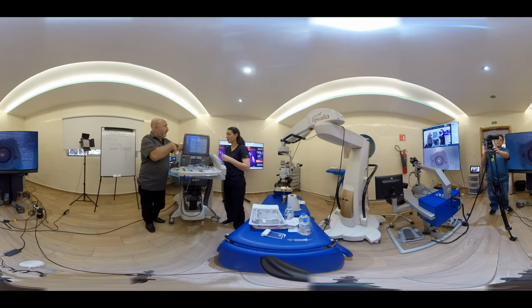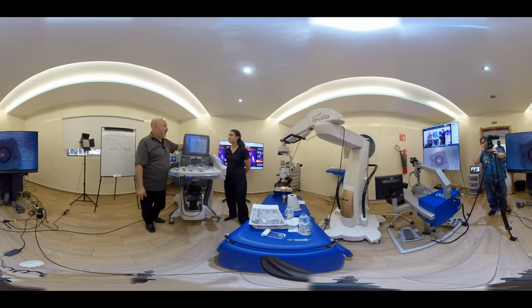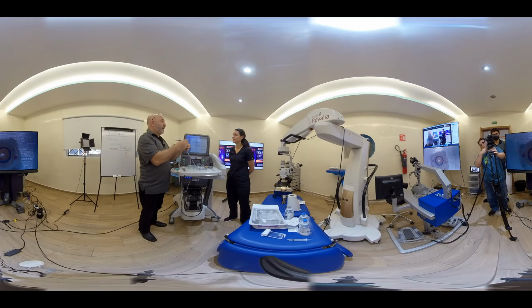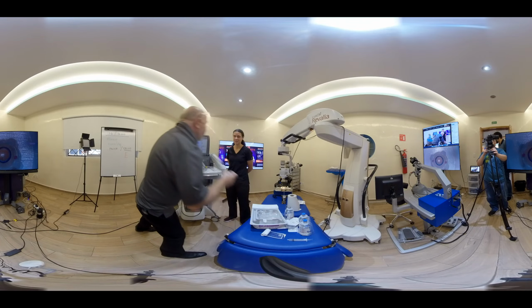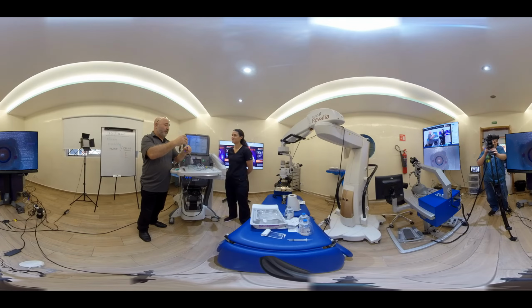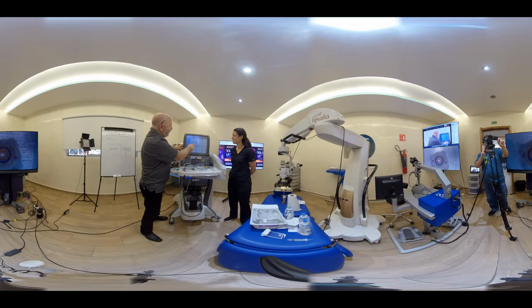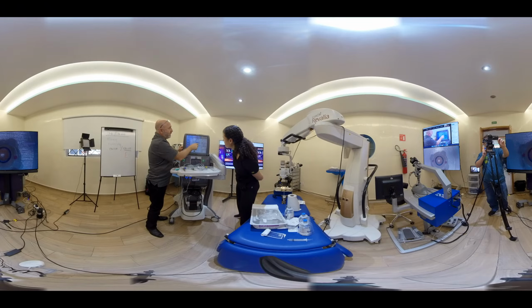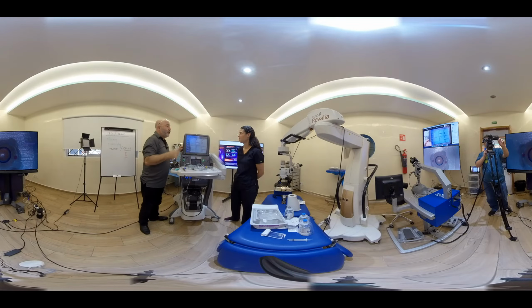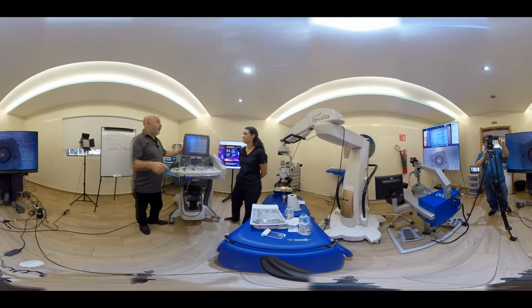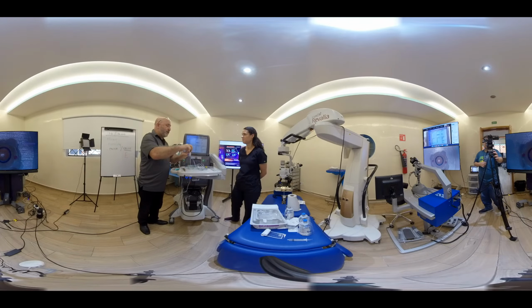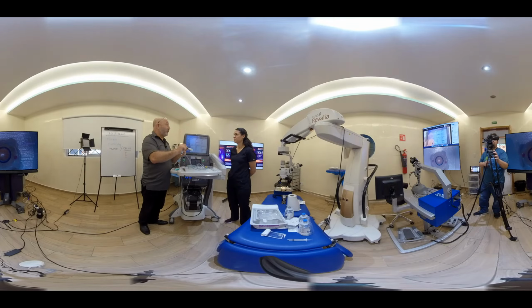From here... Do you prime, calibrate all that first? Yes, I do. Okay, which is what most people do. Yes. But then you end up with fluid in your aspiration line of the vitrectomy probe. Yes. And then you have to syringe out the fluid. Yes. Push all the fluid out so you can take a dry sample. Or you can do something else. Look what we have here in the vitrectomy thing, skip prime. If I press that, knowing that I'm going to do a vitreous tap, it won't prime the aspiration line of the vitrectomy probe, so it stays dry.